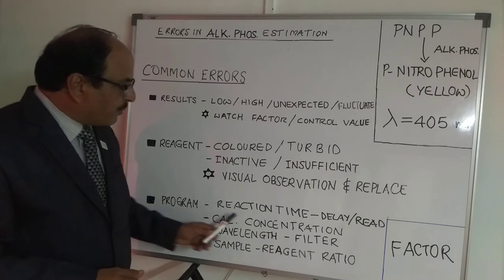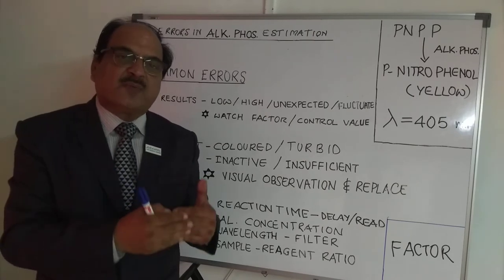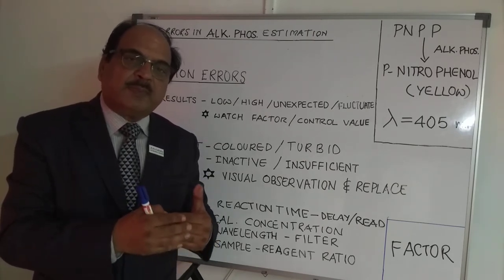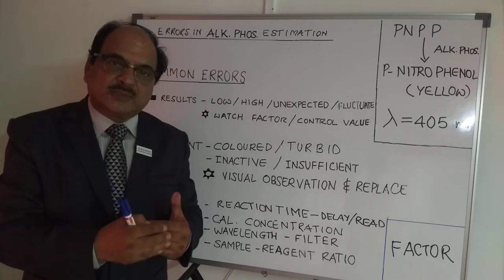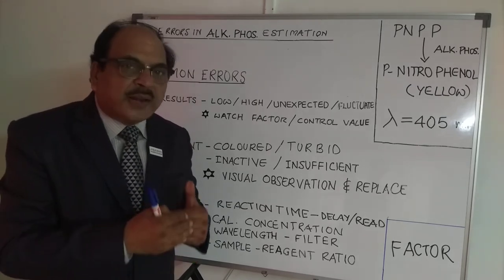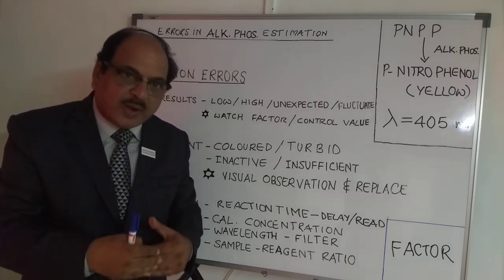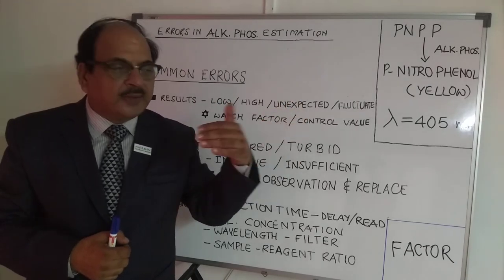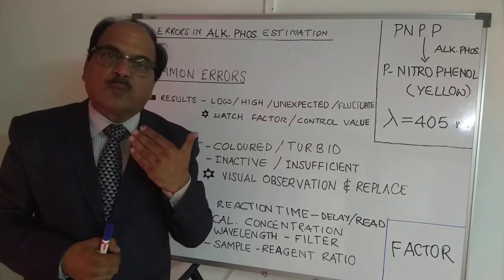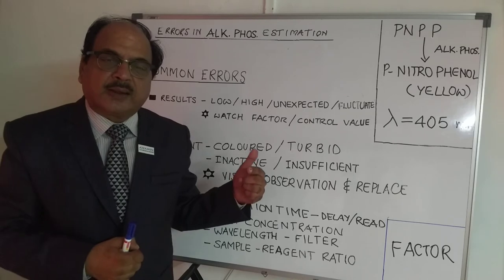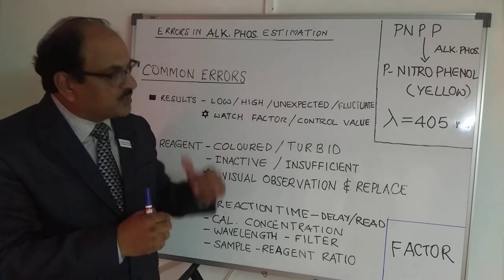One of the most important areas is calibrator concentration. Alkaline phosphatase has many times been given as a fixed factor, but many people use a multi-calibrator. The multi-cal value is lot-specific and method-specific. Very commonly, one tends to forget to update the value in the program when a new lot is used — the previous lot values are continued, resulting in a wrong factor and wrong results. Ensure that the vial's value matches what is entered in the program.